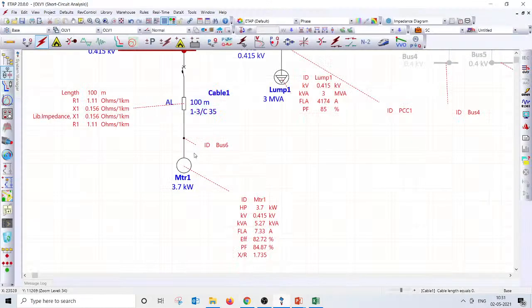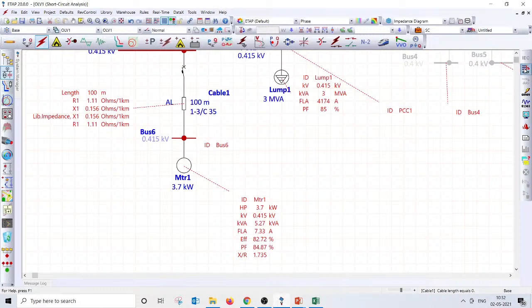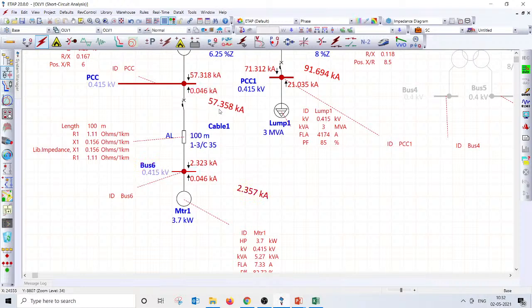So let's run a short circuit study again, but this time with the fault current not only at all the buses but also at the motor terminal, right? Let me convert this into a node to bus, right? Then let's run the fault and look at the fault current. You have interestingly noticed one important aspect: even with the 35 square cable, the fault current of 57 kiloamps came down to just 2.3 kiloamps, just 2.3 kiloamps.